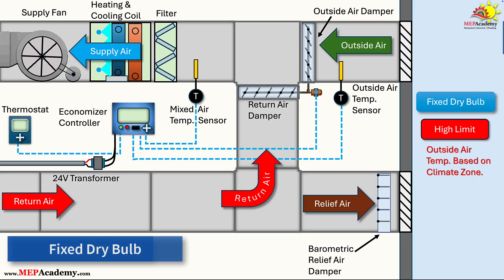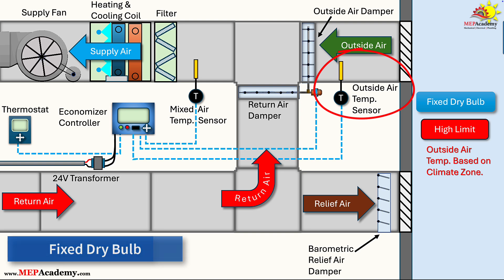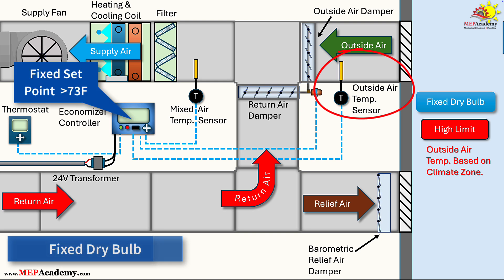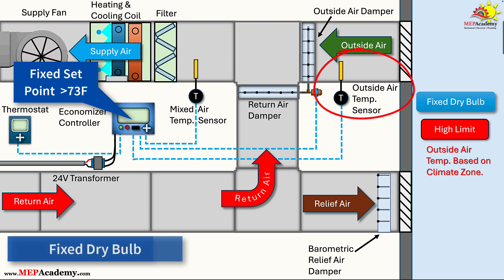Fixed Dry Bulb Strategy. The fixed dry bulb strategy is one of the simplest and most cost-effective high-limit controls for air economizers. It operates by measuring the outdoor air dry bulb temperature – the air temperature without considering humidity – and comparing it to a predetermined fixed set point. If the outdoor temperature exceeds this set point, the economizer disables, closing the outdoor air dampers and relying on mechanical cooling. This method requires only a single temperature sensor in the outdoor air stream, making it low-maintenance and inexpensive to install.